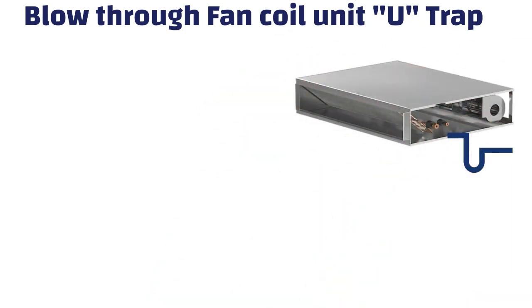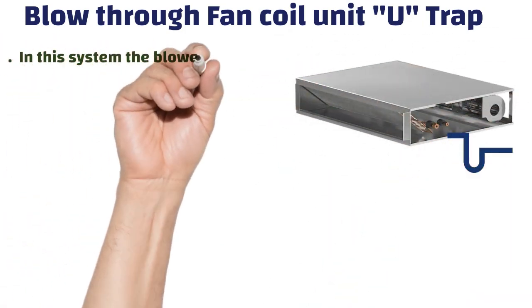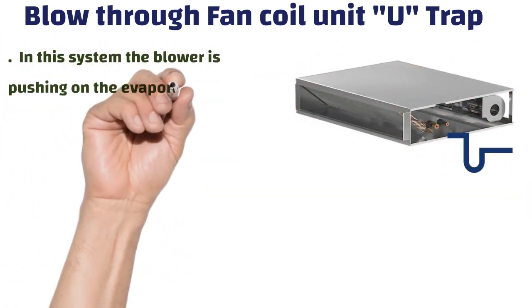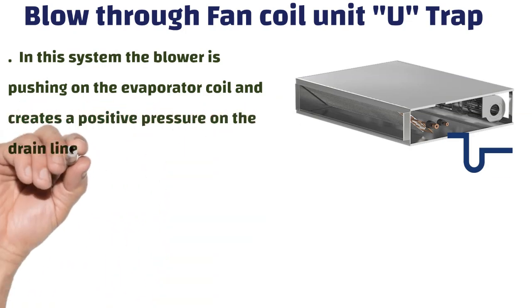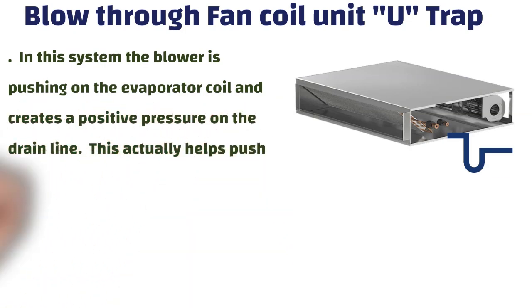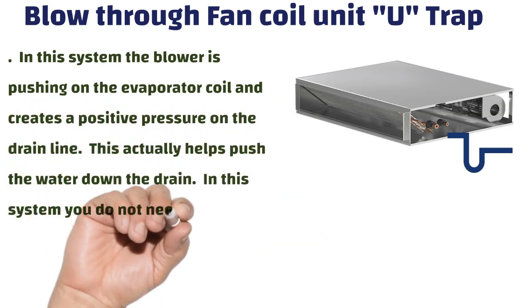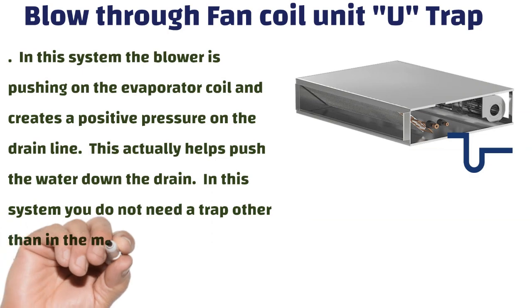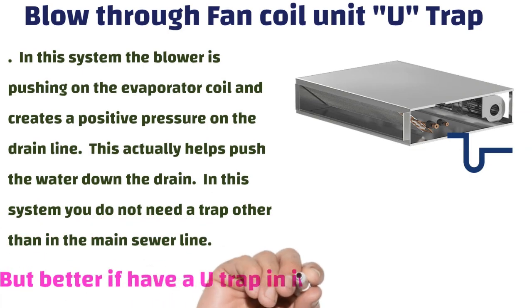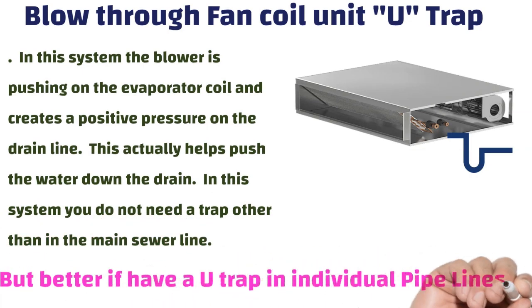U-trap at blow-through unit: in this system, the blower is pushing air onto the evaporator coil and creates a positive pressure on the drain line. This actually helps push the water down the drain. In this system, you do not need a trap other than in the main sewer line, but it is better to have a U-trap in individual pipelines as well.